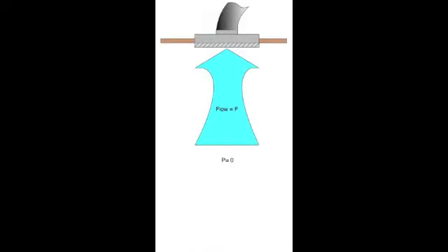So let's apply this concept to a return grill. Our job is to measure the amount of air going into the return. Realize that air flow moving into the return is determined by the pressure difference in the duct, which is a negative number, and the pressure in the room, which is zero. For maximum accuracy, it is important that these two pressures not be changed by the test method.